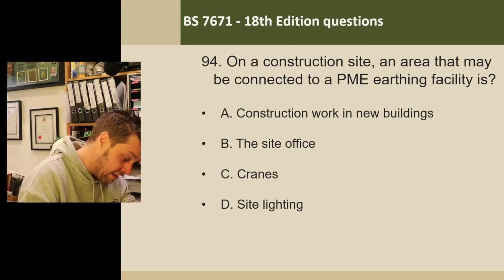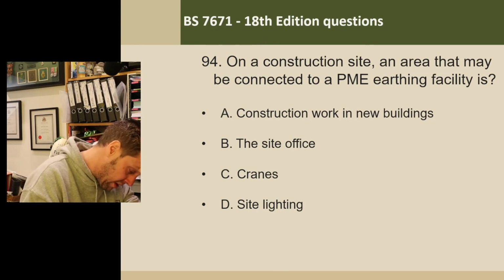A PME earthing facility shall not be used for the means of earthing for an installation falling within the scope of this section unless all extraneous conductive parts are reliably connected to the main earthing terminal in accordance with section 411.3.1.2.